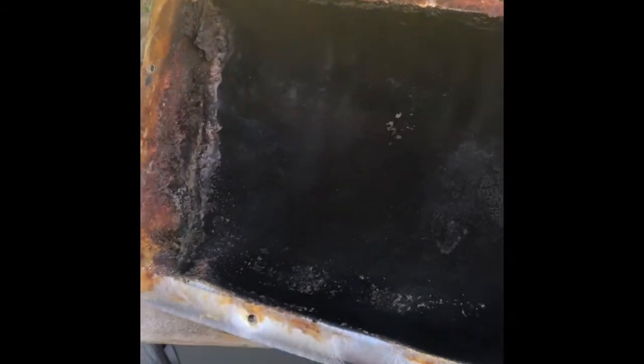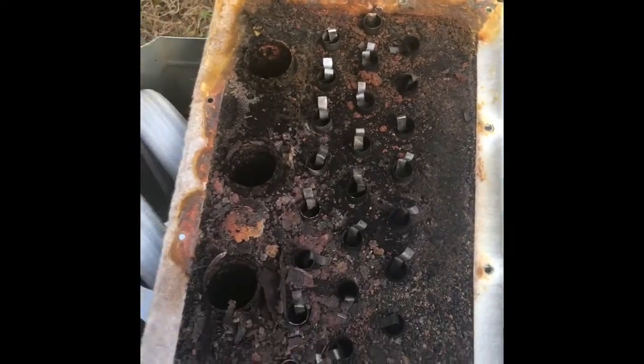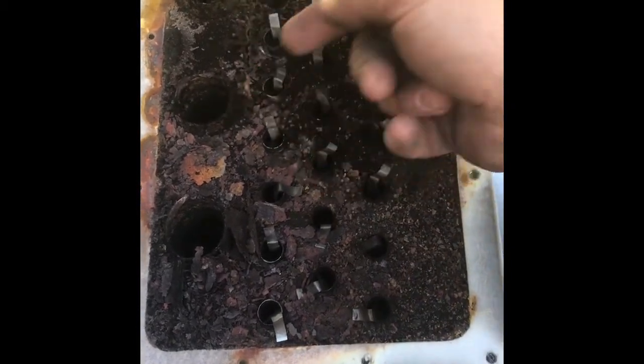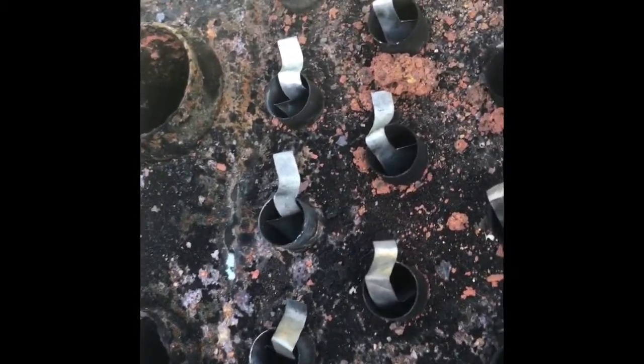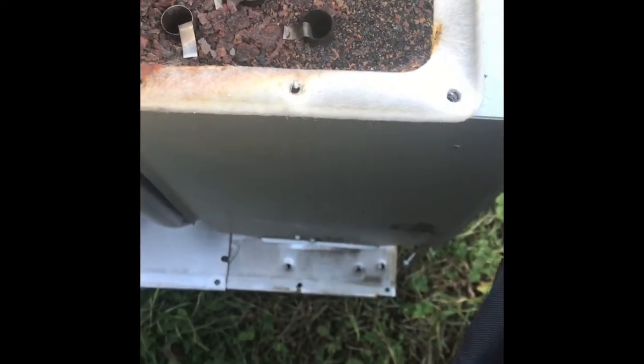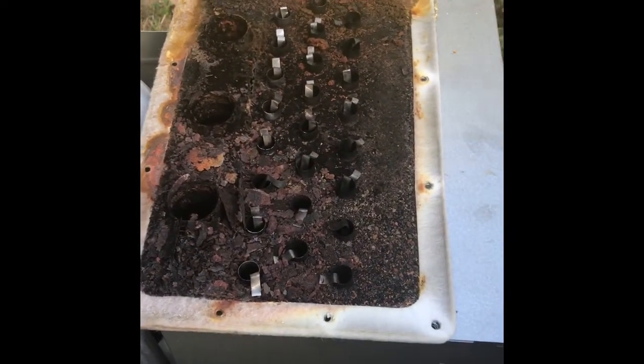There you have it. Look at that cover, look at that secondary. There's a hole burnt right through here. You see that hole? You can see daylight through it. Definitely a failure that you wouldn't see with any camera, unless you were able to get down through the top. If you could get down through the top of the heat exchanger and you knew where to look, you might be able to get down there and notice that separation, but it would be pretty tough.